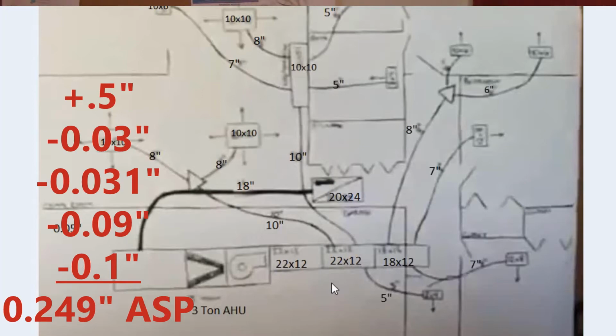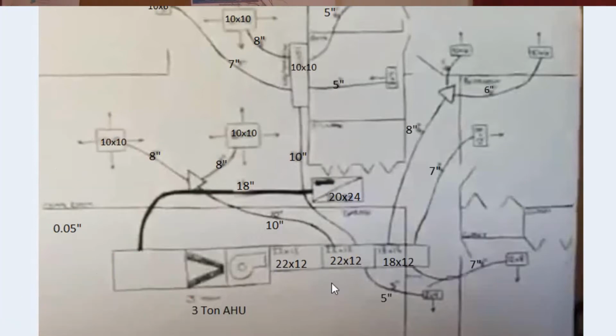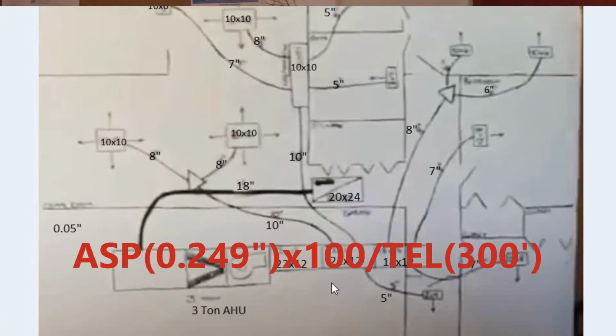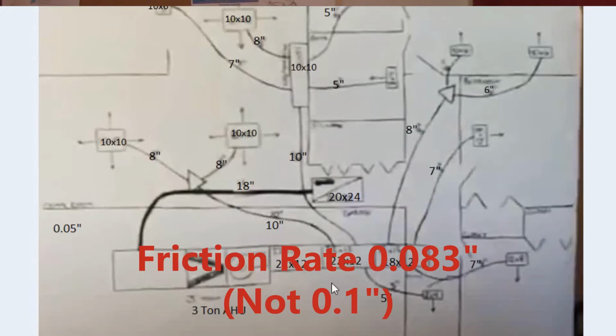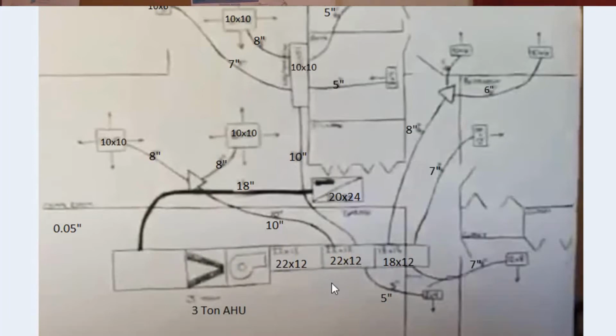So then what do we do? Well, we are going to multiply that times 100. Then we are going to divide that by our total effective length. I'm going to use 300 in this example. And that will give us our friction rate that we are to design this system on. It is a 0.083 friction rate. So that is what we're actually going to size all of our ductwork on.